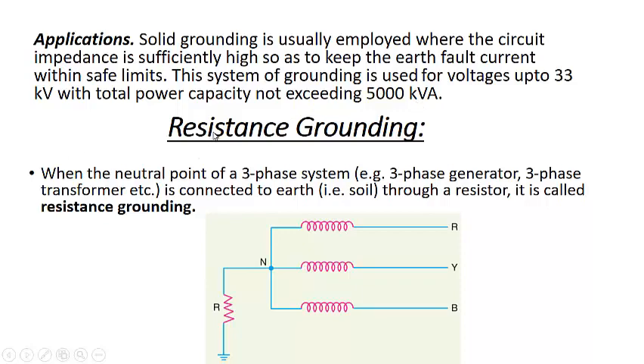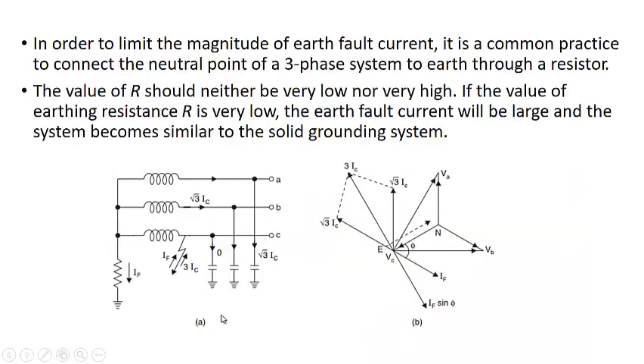Now the second one is resistance grounding. You can see from the name itself, when the neutral point of the three-phase system is connected to earth through a resistance, it is known as resistance grounding, and it is connected like this. It's very simple. So why do we do resistance grounding? In order to limit the magnitude of the earth fault current.